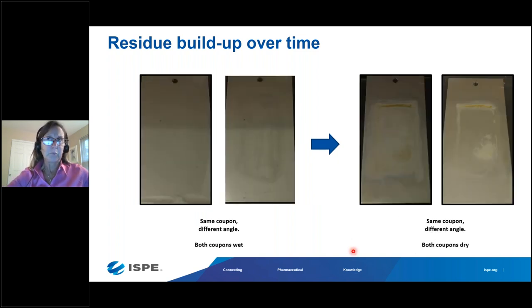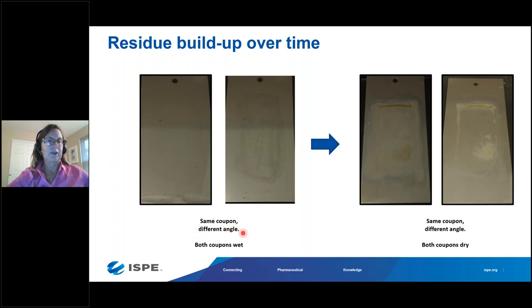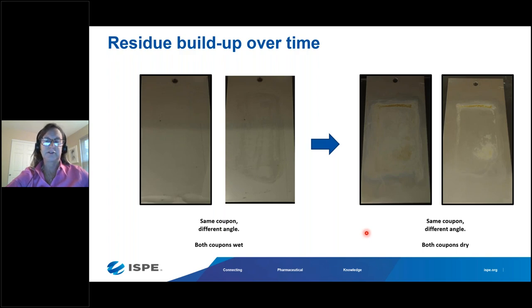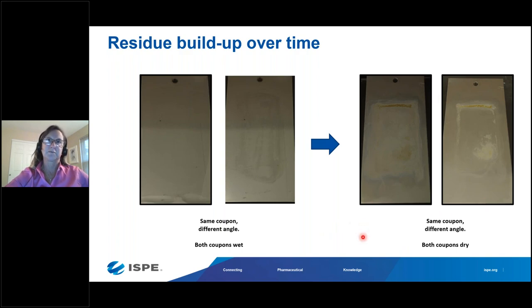When inspecting equipment for visual cleanliness, it is important to look under both wet and dry conditions, but especially dry. The same coupon under different angles when wet may show the residue from one angle but not the other, whereas when dry the residue is visible under both angles. Residues like titanium dioxide and thin mineral films are very difficult to see when wet but are clearly visible once the equipment is dry. The recommendation is to inspect equipment under dry conditions.